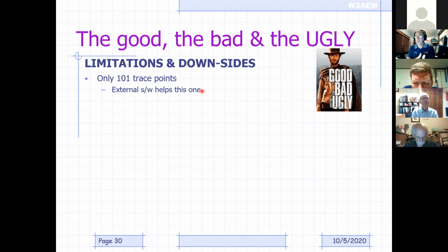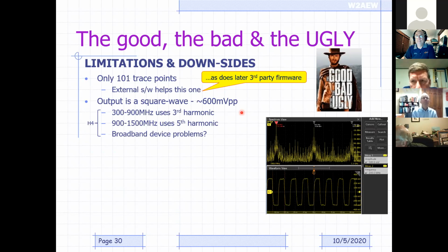The PC can actually ask for measurements over multiple frequency ranges and stitch them all together and effectively get hundreds of points across a sweep. But that means that you're now tethered or tied to a PC to do these measurements. So it depends on your use case whether that's fine with you or not. Again, the third-party firmware, as I mentioned, like that I'm running here, gives me up to 400 points.